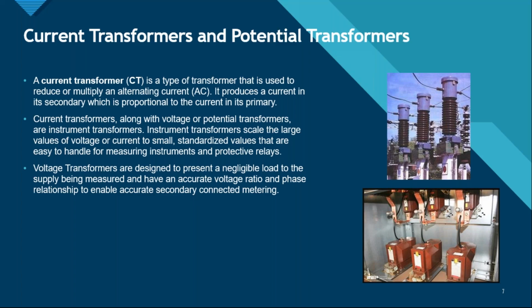The current transformer is connected directly to the bus bar, right? The primary side is connected to the bus bar, and the secondary is connected to the relays. A current transformer is a type of transformer that is used to reduce or multiply an alternating current, right? They have two secondary cores. One is for metering, for measuring the current, and the second is for protection, for giving the command to the relay in case there is a fault. It produces a current in its secondary which is proportional to the current in its primary, right?